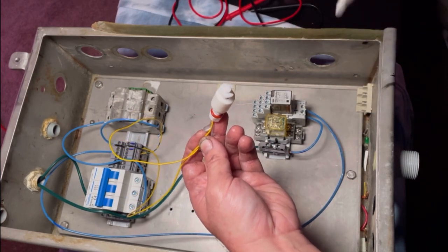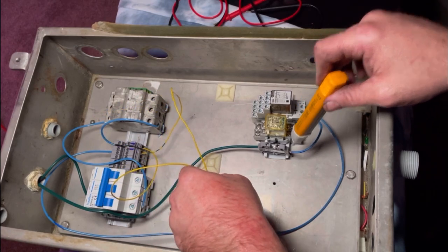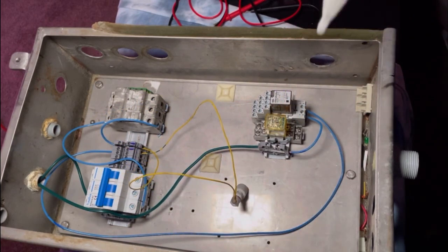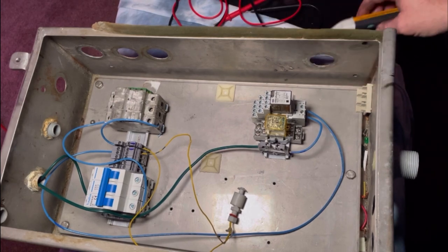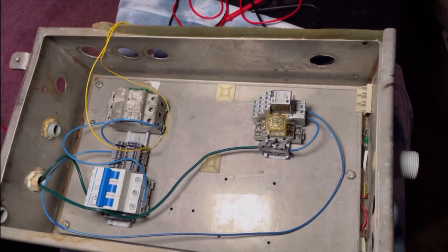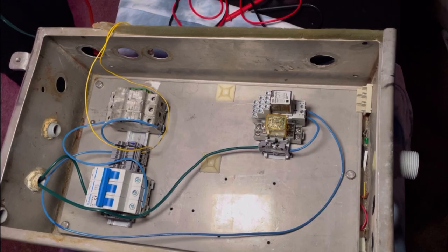So what I'm going to do is I'm going to turn off the power so I can safely do it, and I'm going to make that connection better right there. I did not do that on purpose. It just happened that way. All right, people. Now we're going hot. You see the kind of equipment I'm working with. I'm a little bit leery plugging it in, and I'm flipping the float switch. Do you hear that relay clicking? Do you see the indicator changing? So we have an operational relay that's run by a normally open float switch.